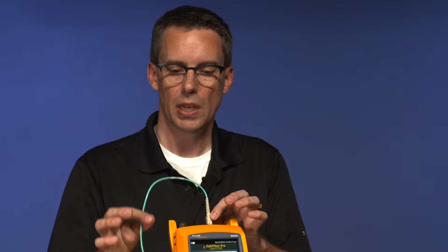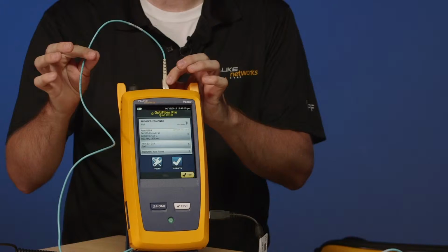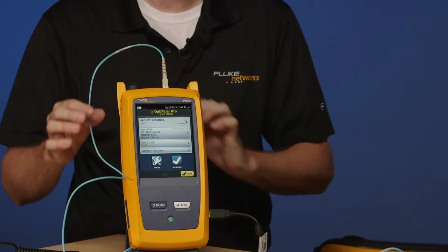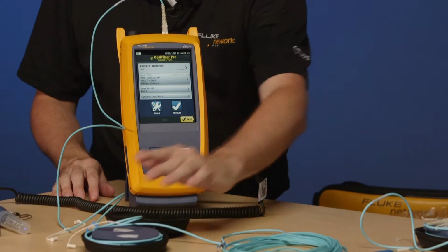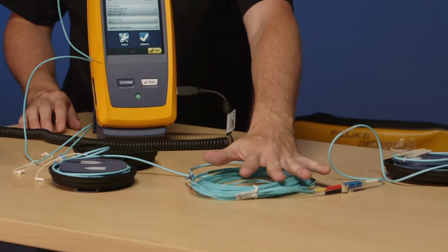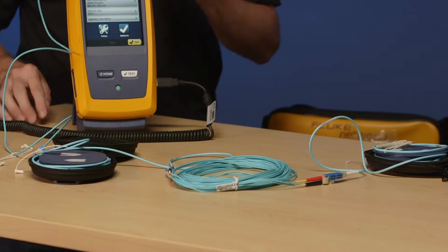So with our launch compensation set, we're ready to run a test. What I've got here is a little sacrificial OTDR port fiber. We'll talk about that in a moment and the reason why I'm doing that. I've got my launch fiber, I've got my tail fiber, and I'm connected to my link under test. And for those of you who saw that OptiFiberPro video I did, this is the same fiber that I'm testing, and there's a good reason for doing that when I download the results later on.